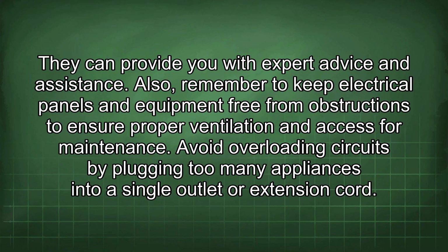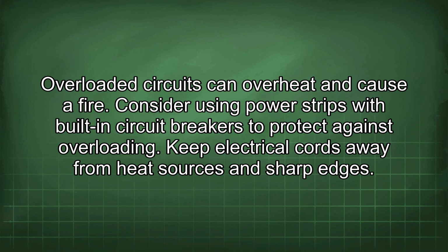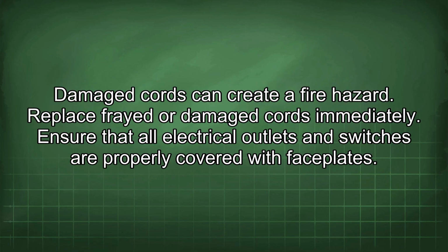Also, remember to keep electrical panels and equipment free from obstructions to ensure proper ventilation and access for maintenance. Avoid overloading circuits by plugging too many appliances into a single outlet or extension cord. Overloaded circuits can overheat and cause a fire. Consider using power strips with built-in circuit breakers to protect against overloading. Keep electrical cords away from heat sources and sharp edges. Damaged cords can create a fire hazard. Replace frayed or damaged cords immediately.